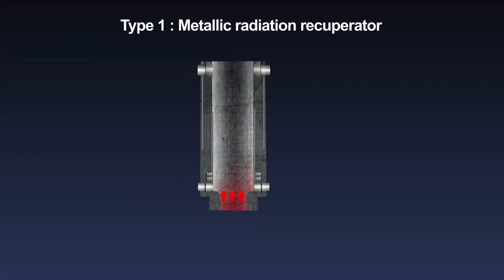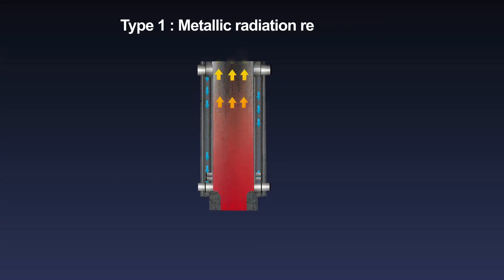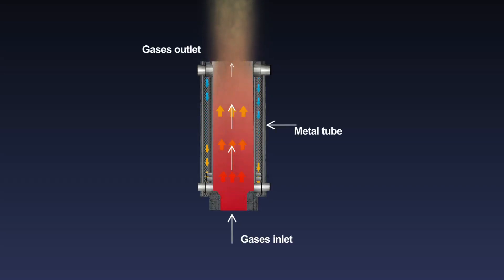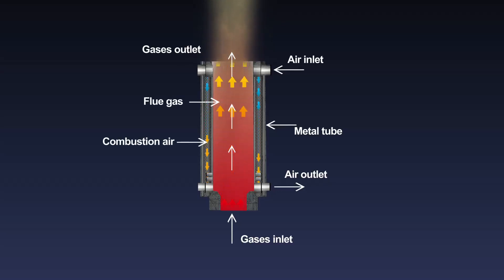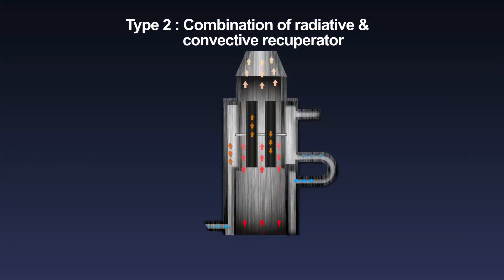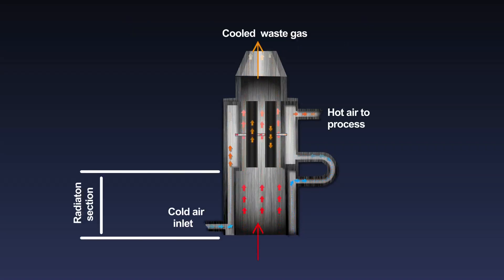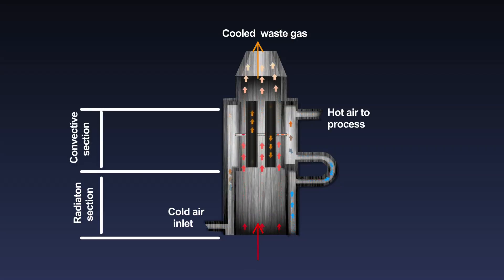A variety of recuperator designs are available for use in rolling mills. The simplest configuration used for pulverized coal fired furnaces is the metallic radiation recuperator, which consists of two concentric lengths of metal tubing. The inner tube carries the flue gas and the outer tube carries the combustion air to be preheated. This type has low efficiency, so to improve heat transfer effectiveness, a combination of radiative and convective designs is used.